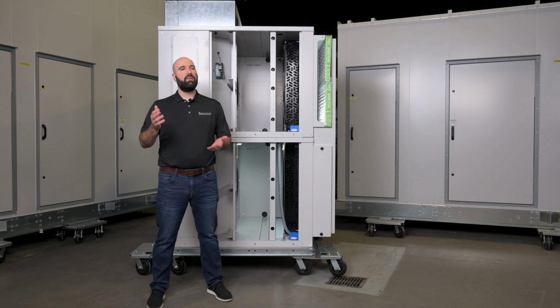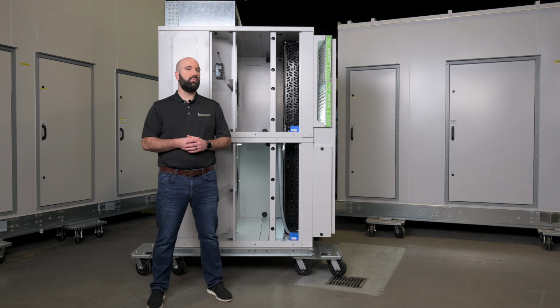Just a quick update in the spirit of our constant product evolution. This Evolution series will shortly be updated with 4 compressors. So there will be 2 compressors in each of the top and bottom deck. And instead of using the Bitzer scroll with VFD combo, we're going back to the Copeland 2-stage compressors on an interlaced evaporator coil. And that's going to provide us 5 stages of cooling in every Evolution unit, at least every Evolution unit that's larger than 25 tons, and provide much tighter control to your space, more parts commonality with other product that you may have on that, and ultimately just much tighter control.